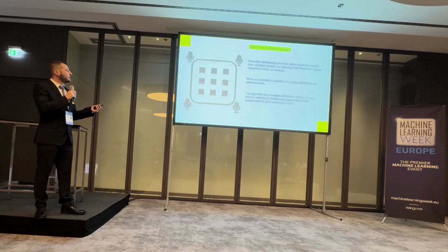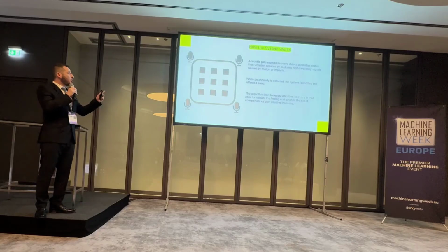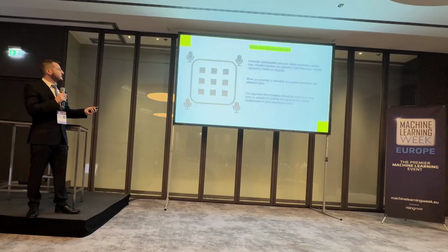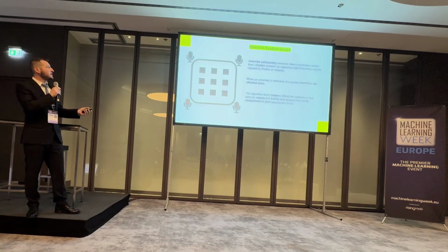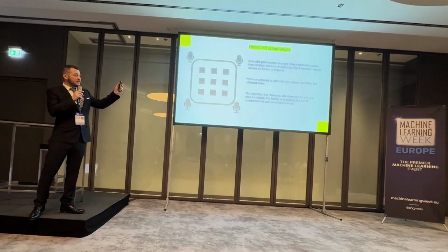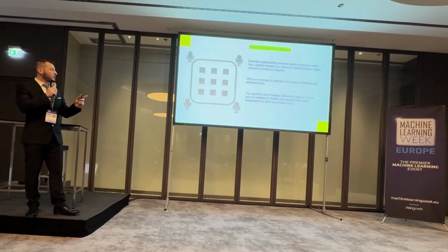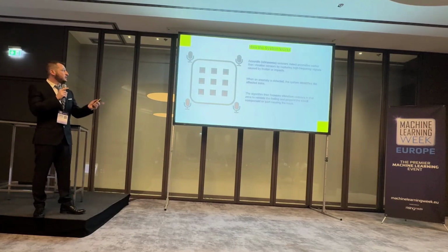So now we're receiving from here, in normal circumstances, every 10 seconds, but this receives every 200 milliseconds. That means that when this detects something, we increase the frequency that we're receiving data only in the part that the acoustic sensor points to. So we increase the frequency that we're receiving from these vibration sensors. What that meant in reality is that from 800 euro per machine, we went to 40 euro, 20 times less expensive in cloud cost because of this trick.